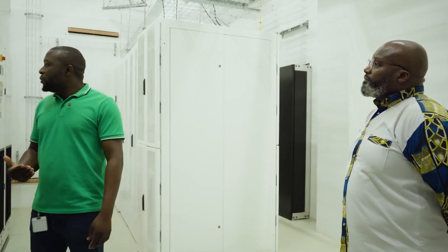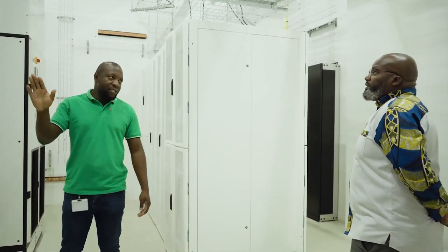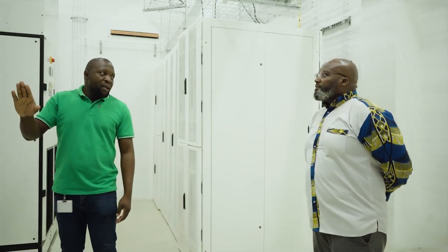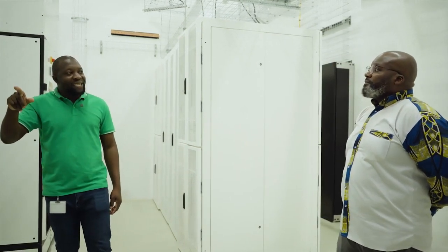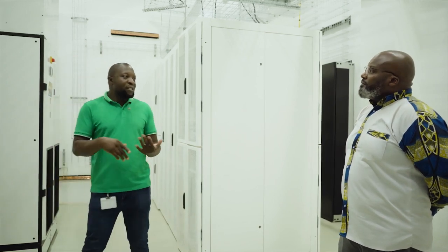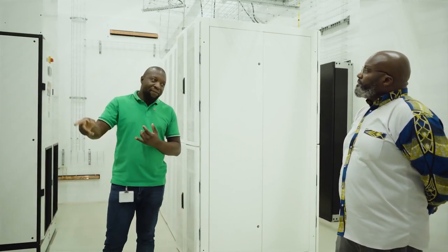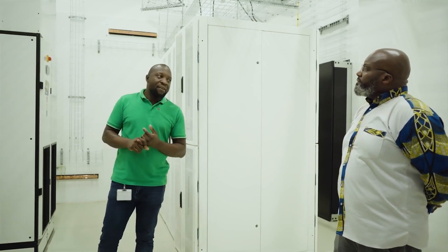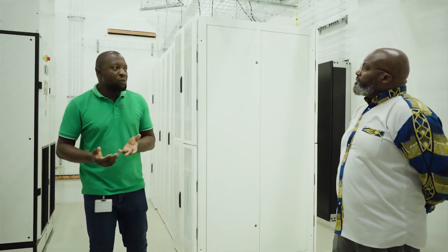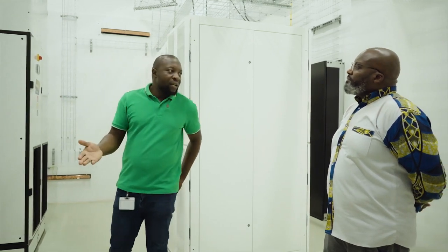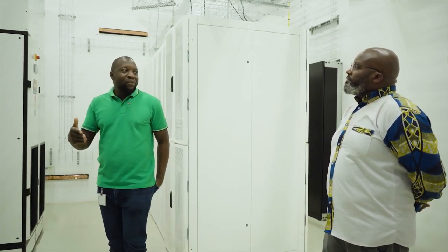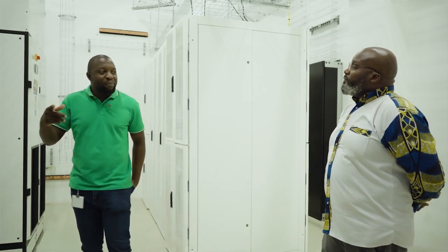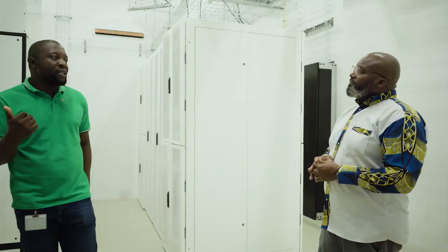So when you want to cool this room using water, because we have two modes of cooling for these coolers, if you want to use water, it means you are using free cooling, not DX. I'm talking in terms of efficiency, because if you're not running compressors to drive the refrigerant along the circuit, it means you're very efficient, because it's only compressors that consume a substantial amount of energy in cooling units. So when you're running on free mode, you're running on water alone, just running through a pump. With no refrigeration? No refrigeration, the compressors are off. And we can only use this mode of cooling if the ambient temperature is low enough to provide the cooling that we require. So the cooler days?